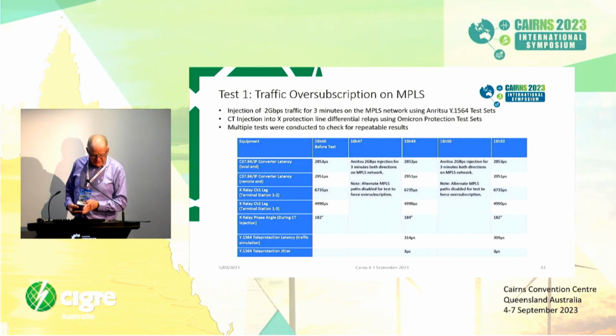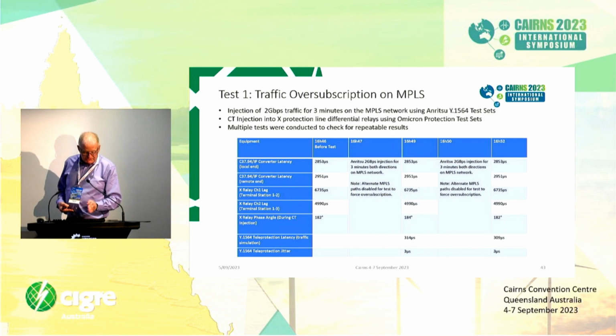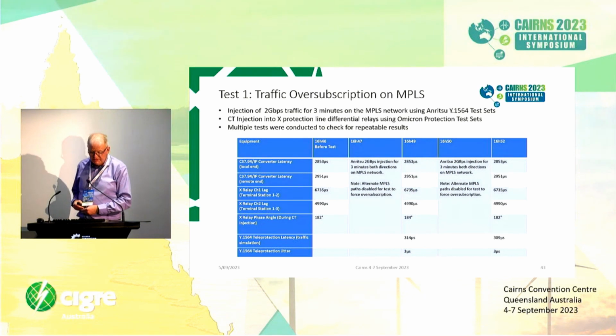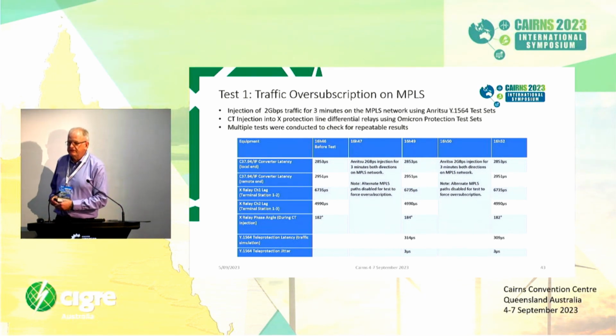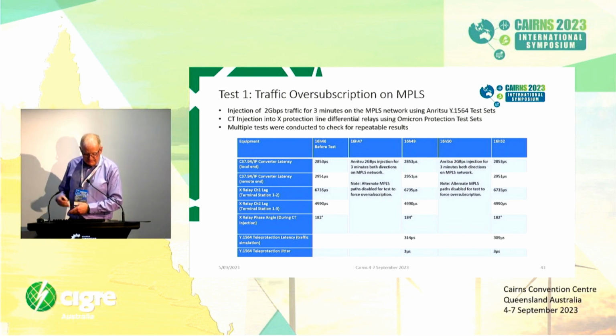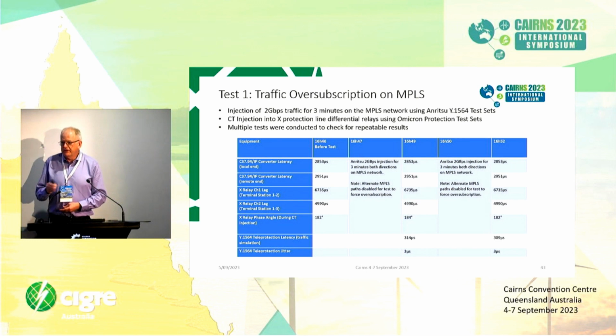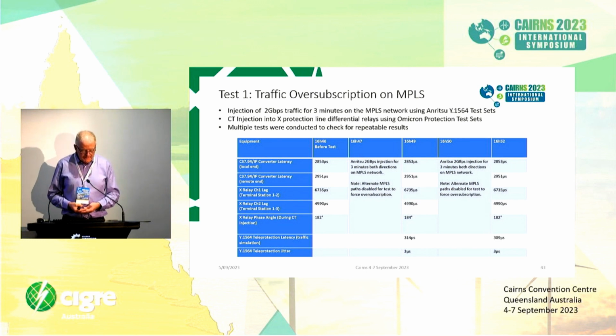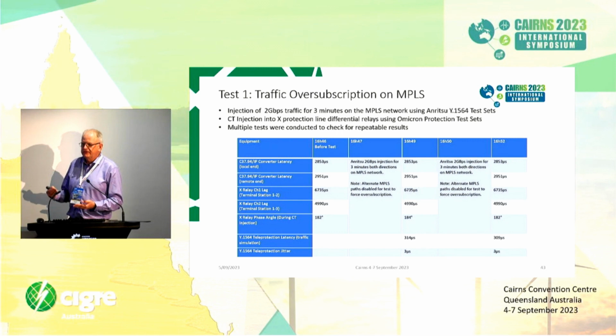The important thing to note here though is down the bottom there, during the actual injection, we saw no real observed difference in the teleprotection latency or jitter, okay? So we got a pretty consistent 314 microsecond latency during the first test and then 309 microseconds of latency during the second test, which is pretty minimal. The jitter remained consistently around that 3 microsecond level throughout the entire test, and that's the normal background jitter figure we see on the network. So this really indicates that all of our quality of service parameters are working correctly. All the teleprotection traffic is obviously high priority traffic.